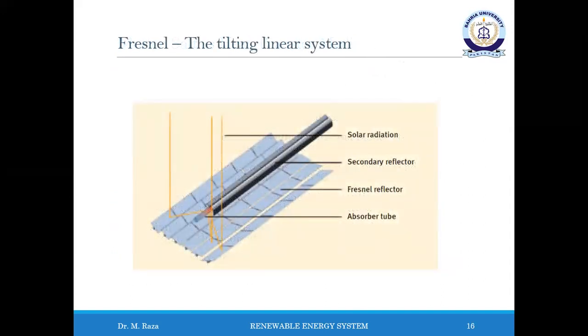An alternative to parabolic trough technology is provided by Fresnel systems, which currently operate with a worldwide capacity of about 45.5 megawatts. The production costs are less than for parabolic trough. The weaker concentration of the solar radiation means that Fresnel collectors have higher optical losses, which reduce the efficiency. The Fresnel collectors are linear concentrating systems with a receiver which, in contrast to parabolic trough plants, does not track the sun.